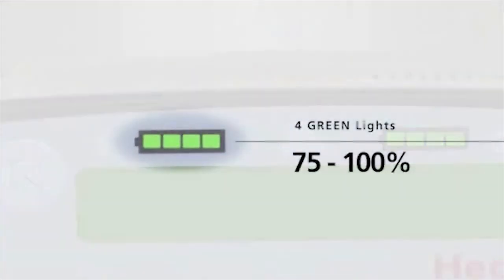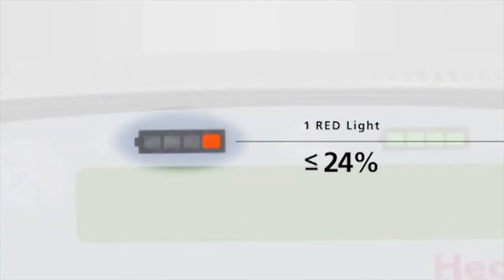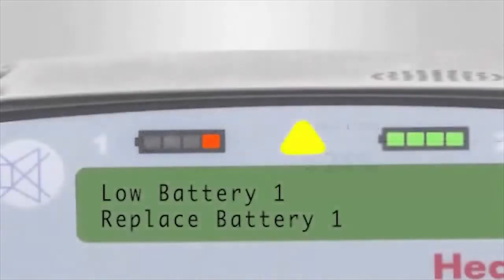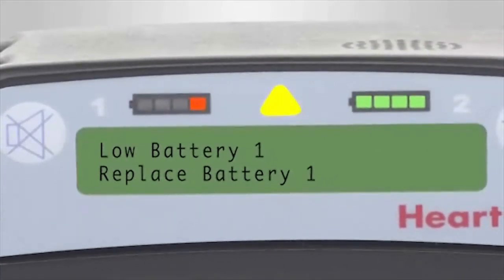Each fully charged battery provides about 6 hours of use for normal activities. When one battery is depleted to 24% capacity, the controller will automatically switch to the other battery. An intermittent beep will sound, the alarm indicator will be yellow, and a message will be displayed on the controller screen to replace the depleted battery.